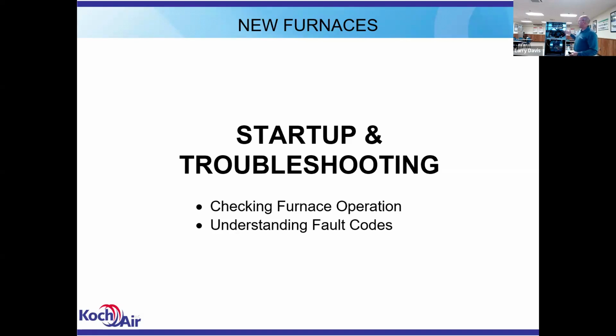So if you are in a downflow install, or an upflow with the coil sitting right on the furnace with no spacer in between, you can pull the limit switch out and put your static pressure probe in there to get your discharge static pressure. So you measure the supply static and the return static, ignore the plus and minus sign, and add the 2 numbers together. That's your external static pressure.